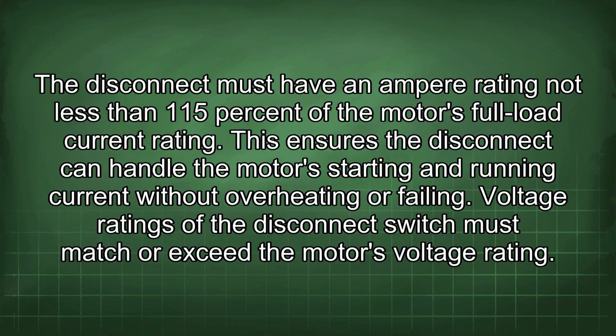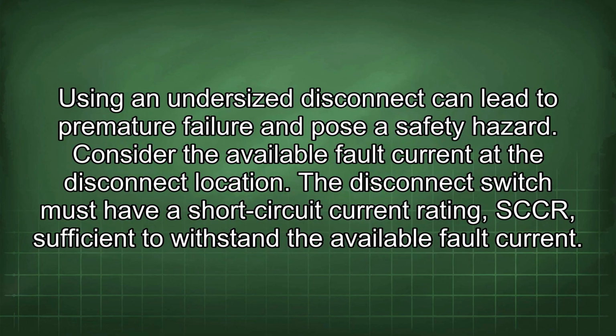The disconnect must have an ampere rating not less than 115% of the motor's full load current rating. This ensures the disconnect can handle the motor's starting and running current without overheating or failing. Voltage ratings of the disconnect switch must match or exceed the motor's voltage rating. Using an undersized disconnect can lead to premature failure and pose a safety hazard.